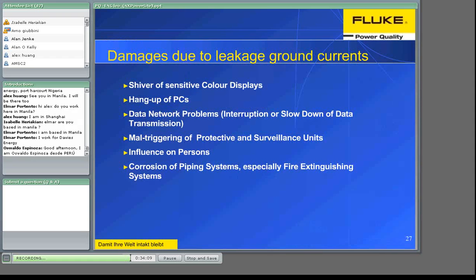Damages owing to leakage ground currents. Display can be affected, hang-up of PCs, data transmission can be affected. Wrong triggering of protection influences on person and the corrosion of piping system, especially by, in this case, DC current.